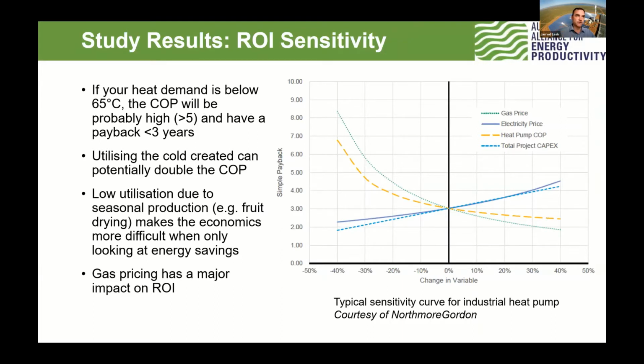Huge potential here. We also see that if you utilise the cold generated from a heat pump, the COP potentially doubles, again with great paybacks. We also see low utilisation for seasonal production being a major contributor to the return on investment for heat pumps - if you're drying fruit on a seasonal basis, that has a big impact, so there's a lot you need to do to optimise the design in that case. And as you see from the graph, the cost of gas has a major impact as well.